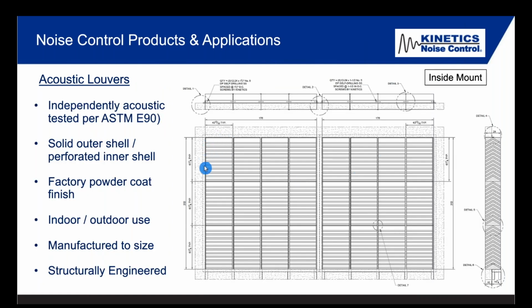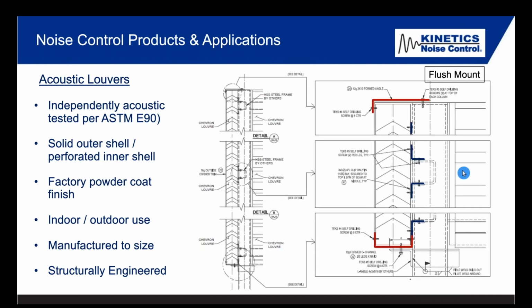You can see a large bank of louvers. This is roughly 200 inches tall and 180 inches wide, 24-inch deep. A lot of smaller louvers are banked up in these spaces. You see a lot at the data centers. You go down the highway and you see many of these openings. In many cases, they have to replace weather louvers and put in acoustic louvers.